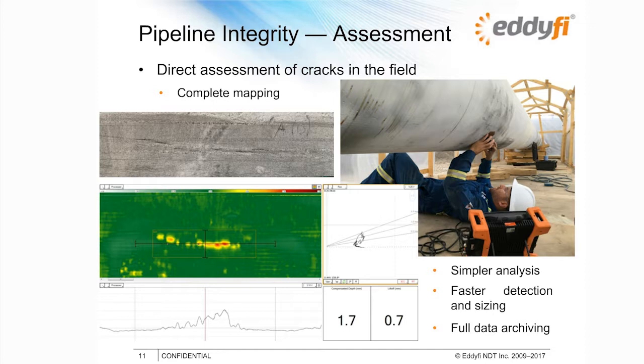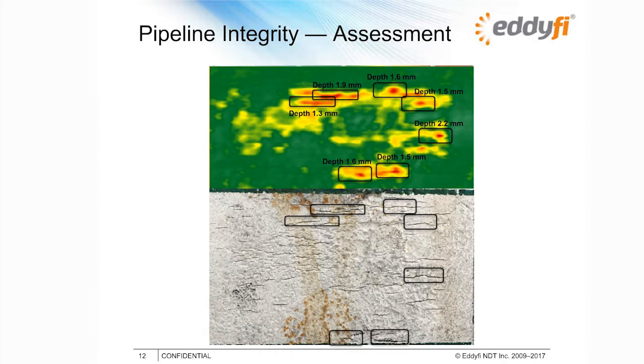Here is a straight comparison of data collected with both TECA and magnetic particle testing. The map you can see here is very similar to magnetic testing, with the added value that we could measure the depth of the different areas cracked around it. So it's a perfect match.